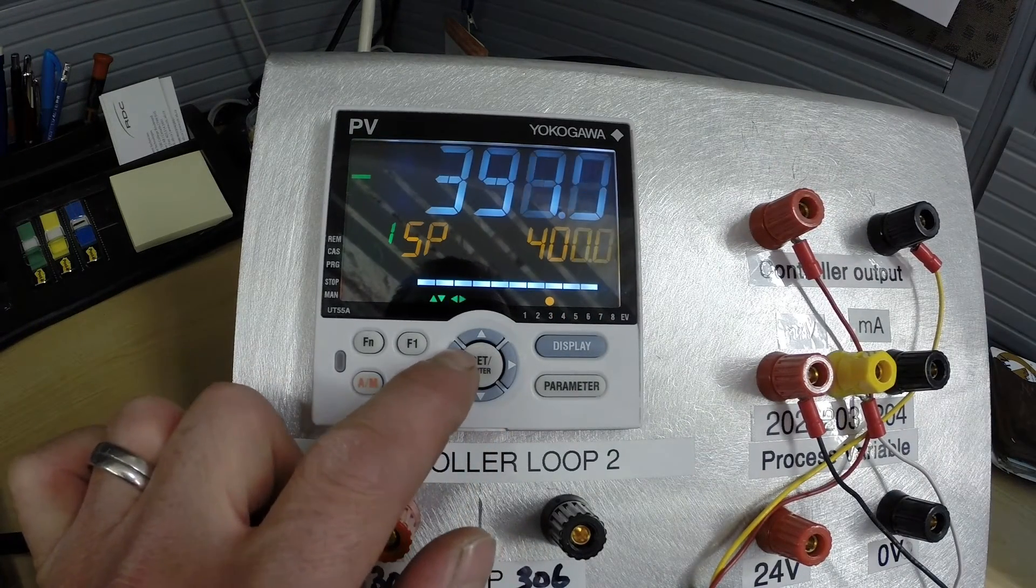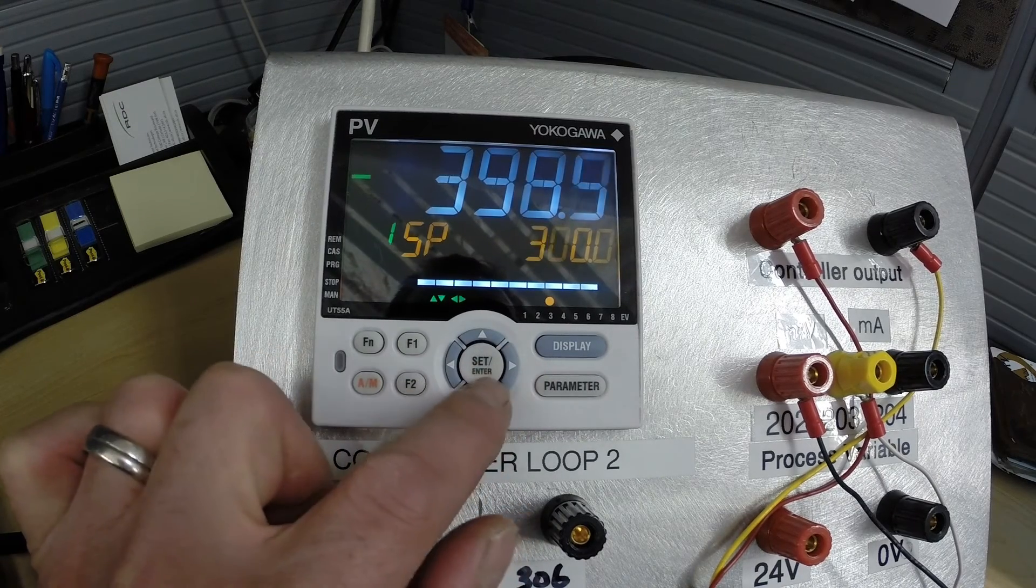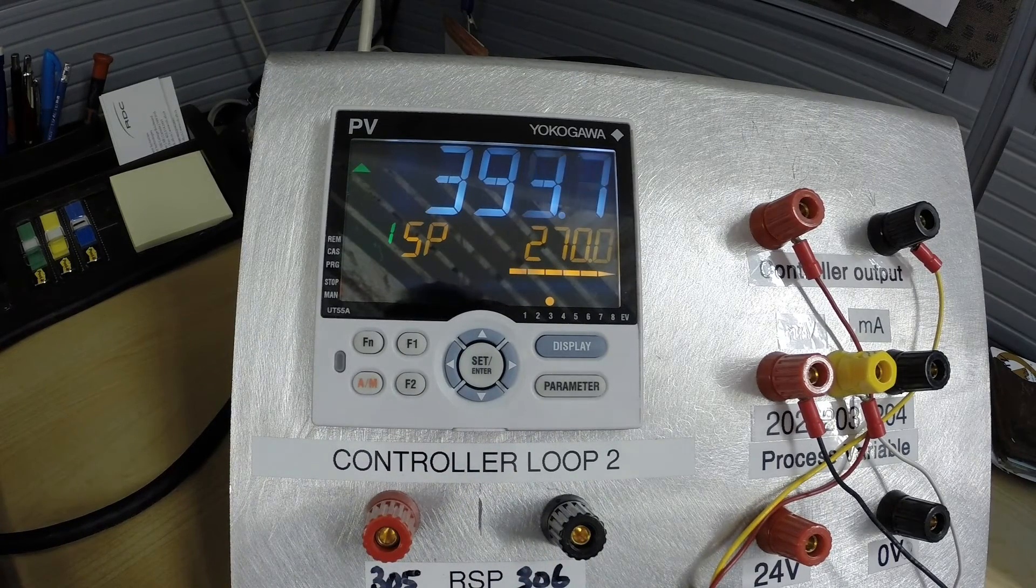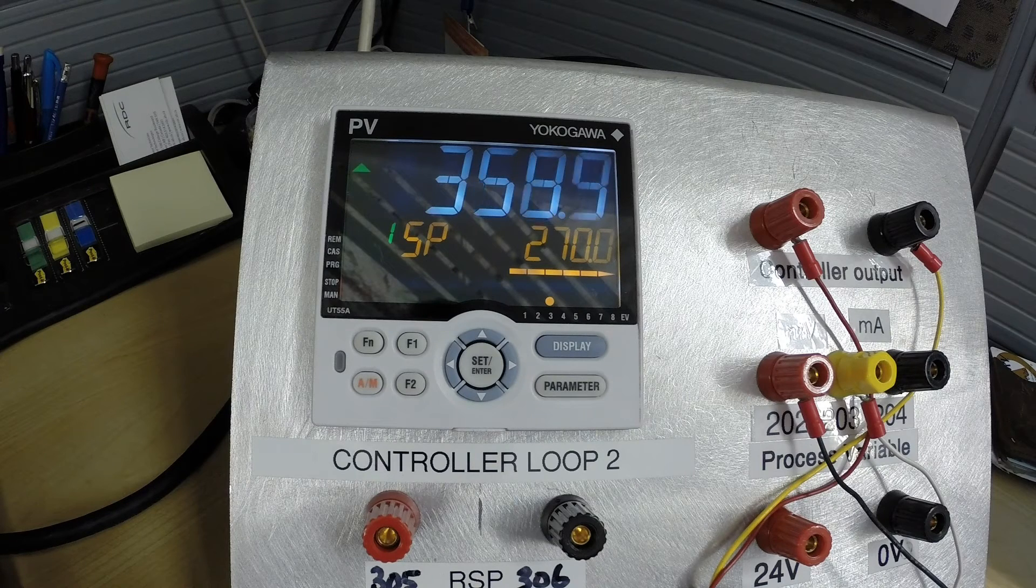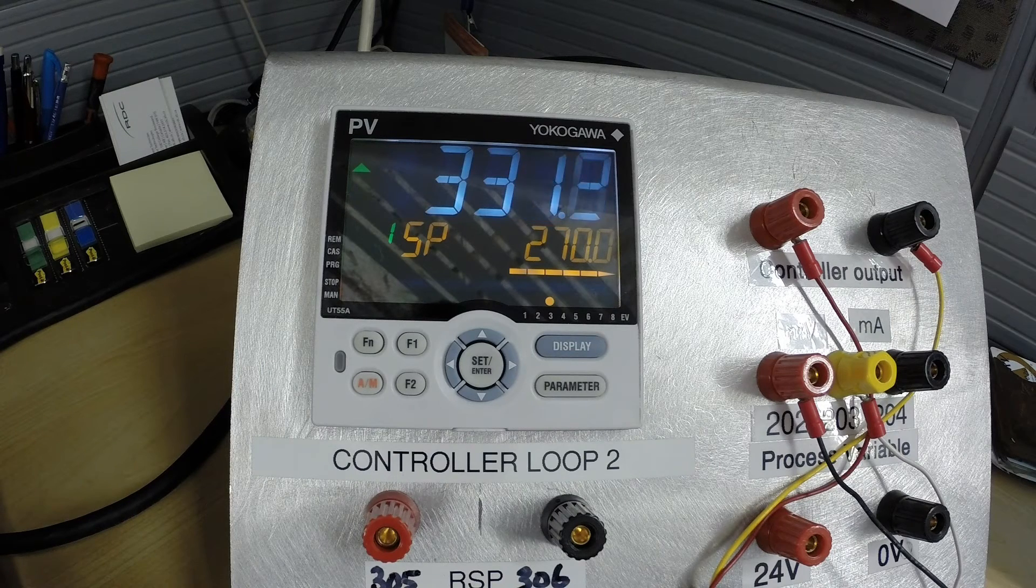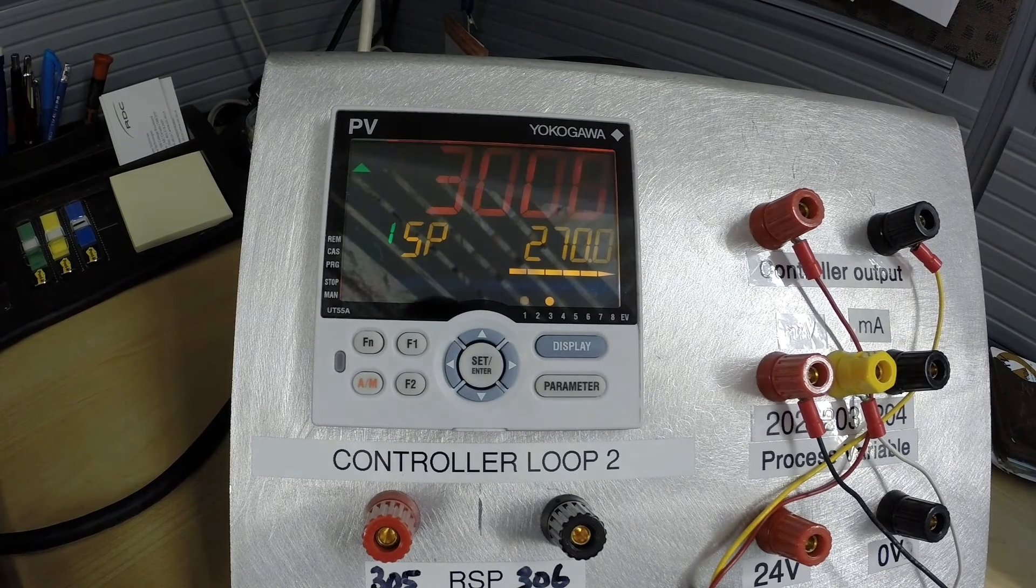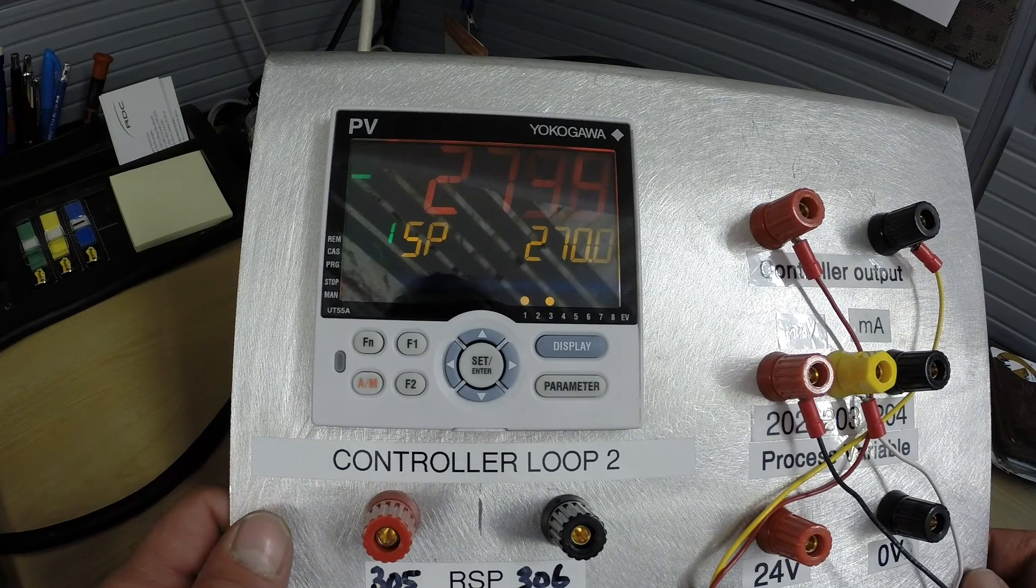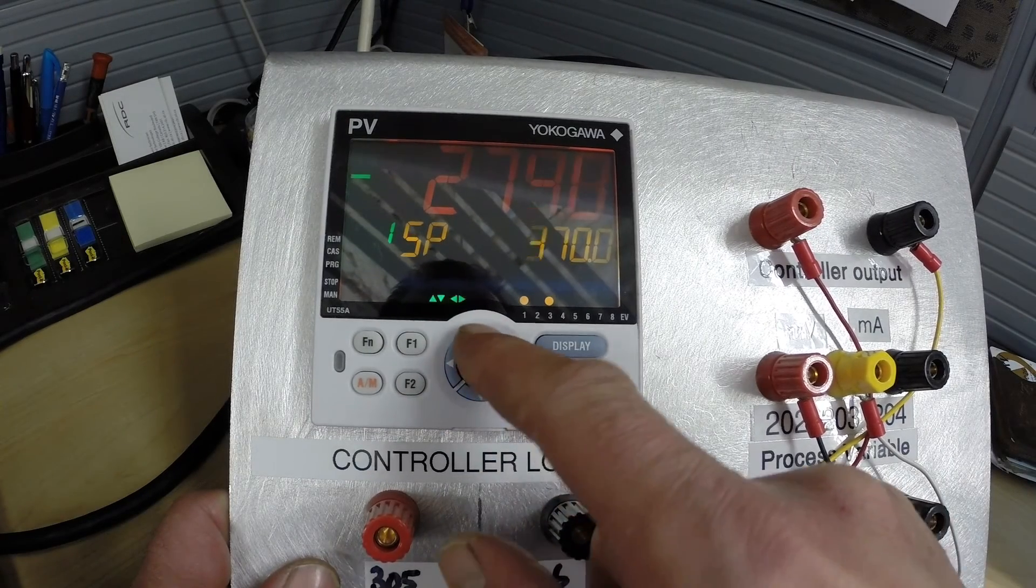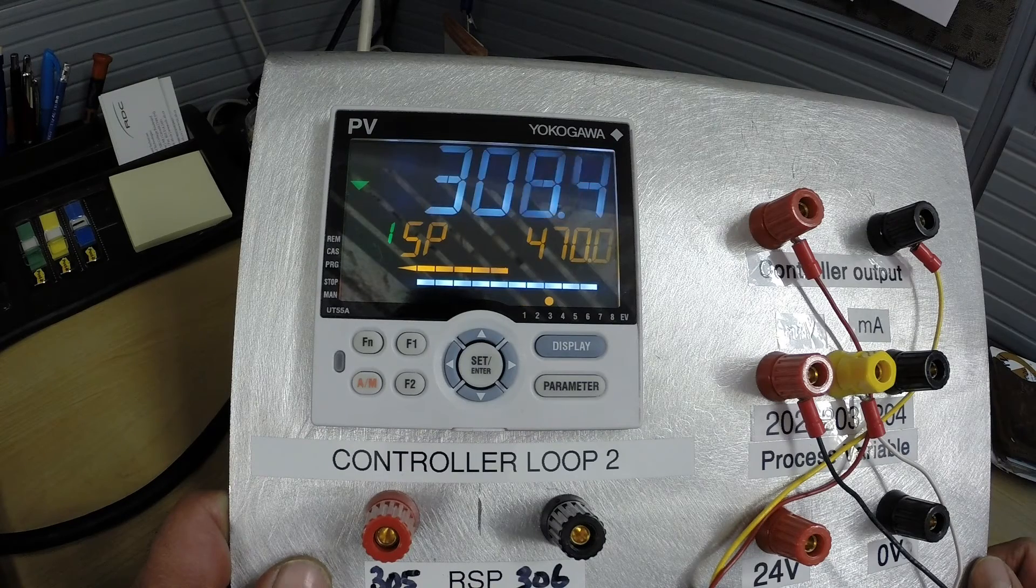Let's change our set point to a value less than our alarm set point which was 300. So let's set it down to oh let's go 270 and press enter. Let's watch and see what the controller does. With any luck it should turn red at 300 degrees. I'll come back in a minute oh there it is already so you can see that once we drop below our low set point of 300 degrees the display changed to red which gives the operators a visual indication that they are in fact in alarm.